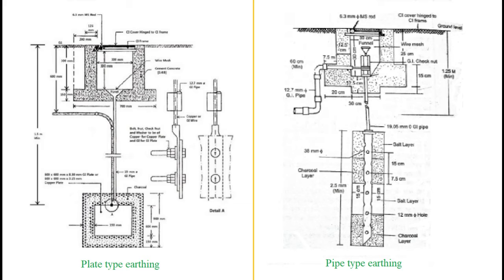One is plate type earthing and the other is pipe type earthing. For small voltages like 230 to 400 volts, plate type earthing is sufficient, but an 11 kV system requires pipe type earthing. For both types of earthing, maintenance is needed to keep the earth electrode in a wet condition so that it remains at zero potential. A water pouring facility is provided at each earth pit, below which the earth electrode is buried in the ground. Let us understand the constructional details of the two types of pits one by one.